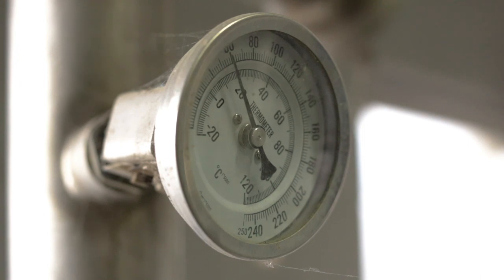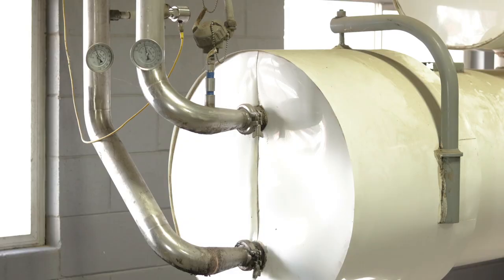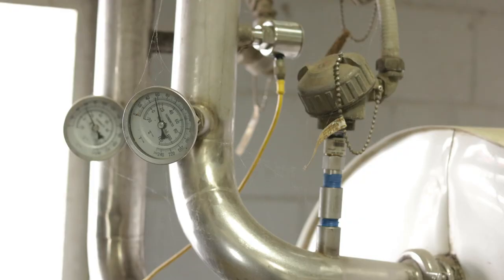The heat exchanger must have sufficient instrumentation for monitoring the heat exchanger operating conditions per Item L in the checklist. Heat exchangers should have a pressure gauge to monitor the ammonia pressure. The secondary coolant will often have inlet and outlet temperature probes as well as pressure gauges for any associated pumps.